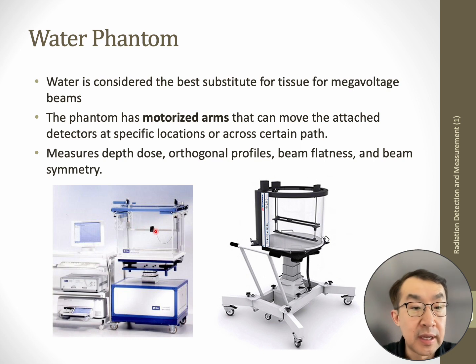When you attach a detector to one of the detector holders, you can remotely control the movement of this detector holder, left, right, up, down, or in and out, diagonally. So it is best suited for measuring depth dose and orthogonal profile or beam flatness.